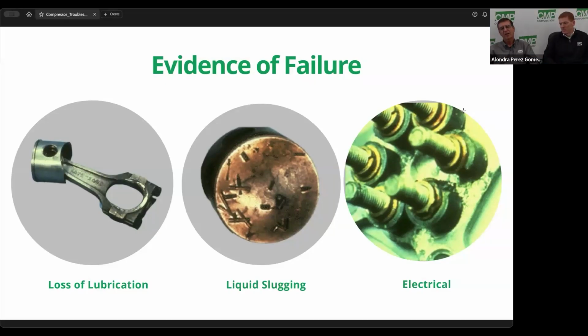Absolutely. And also, if it breaks a valve plate, a discharge reed, or blows a valve plate gasket, the compressor sometimes will vibrate and shake violently there. You would think there's something wrong with the compressor that can't be fixed, but sometimes just changing the valve plate fixes it. But if you think about it, it throws the balance off of the compressor because the gas is seesawing back and forth in that valve reed where it's supposed to be. And that's what causes your heat on there. But yeah, it'll cause vibration.